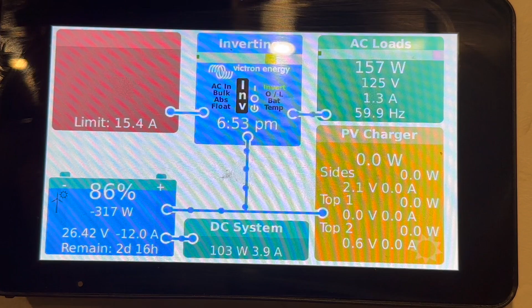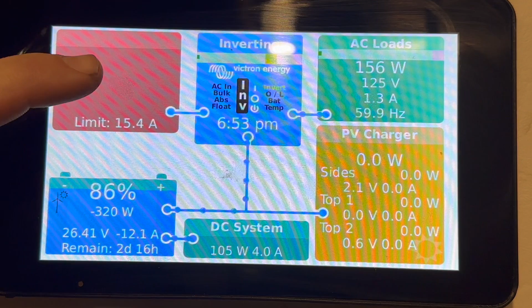So the next tip is adjusting your AC input current limit a little bit lower, about 5% below the limit of your input source. Now I'll show you my different input current limits here using GUI mods. It's important to understand that when you set the current limit, the MultiPlus will many times pull exactly that much current.